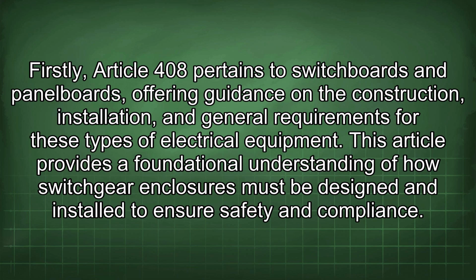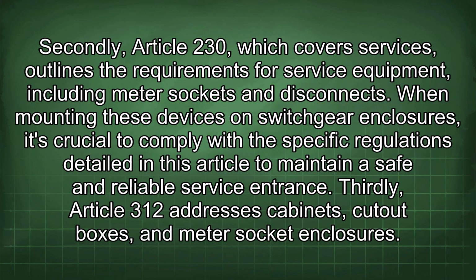Firstly, Article 408 pertains to switchboards and panelboards, offering guidance on the construction, installation, and general requirements for these types of electrical equipment. This article provides a foundational understanding of how switchgear enclosures must be designed and installed to ensure safety and compliance. Secondly, Article 230, which covers services, outlines the requirements for service equipment, including meter sockets and disconnects. When mounting these devices on switchgear enclosures, it's crucial to comply with the specific regulations detailed in this article to maintain a safe and reliable service entrance.